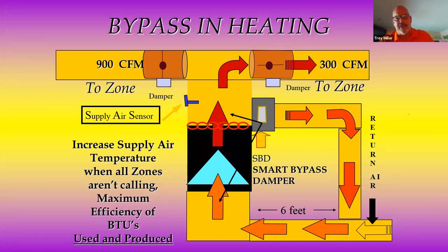This is a beauty, and the beauty of it also is no longer am I giving you a 92, 94, 96 degree discharge temperature. I've increased that discharge temperature to 110 and a little bit above. This is doing nothing but diverting the BTUs to the areas of need rather than having to share them through the entire home. These are tremendous advantages for the homeowner, and as far as the contractor, it makes him look like he's a pretty smart guy, okay? So guys, talk about this. This really excites the homeowner.